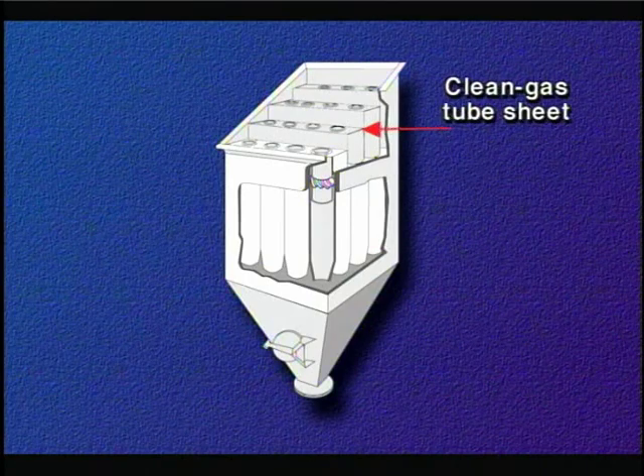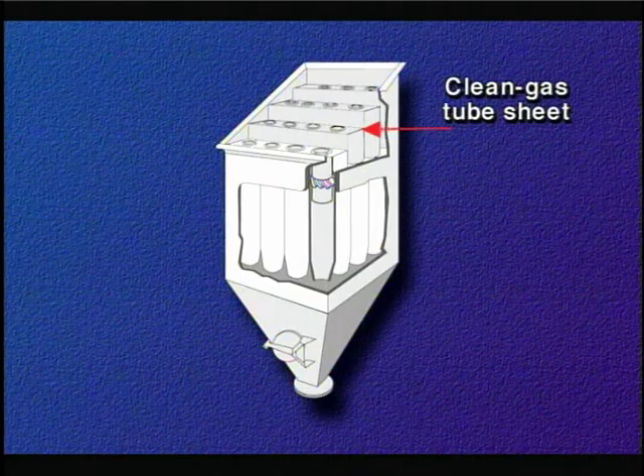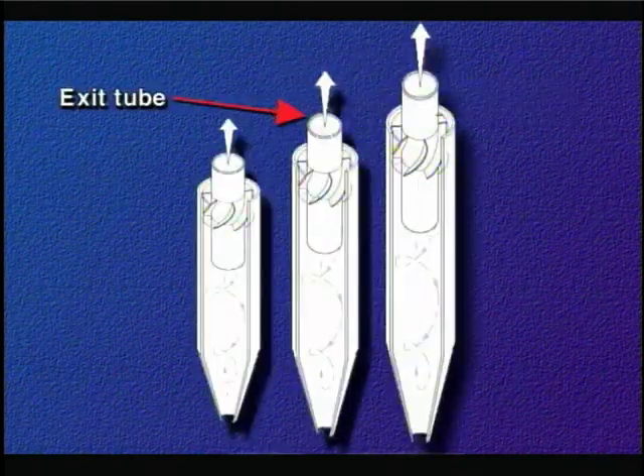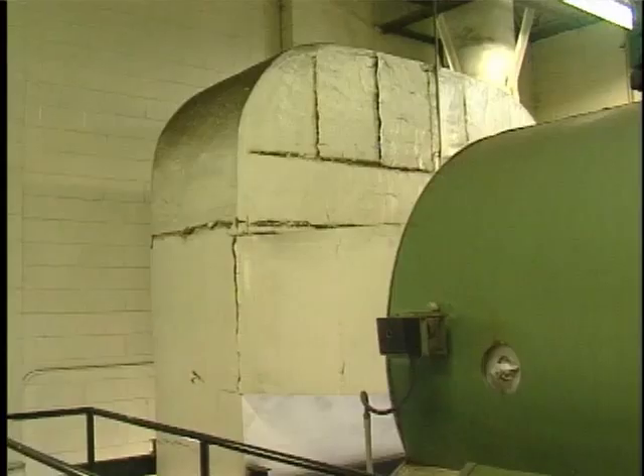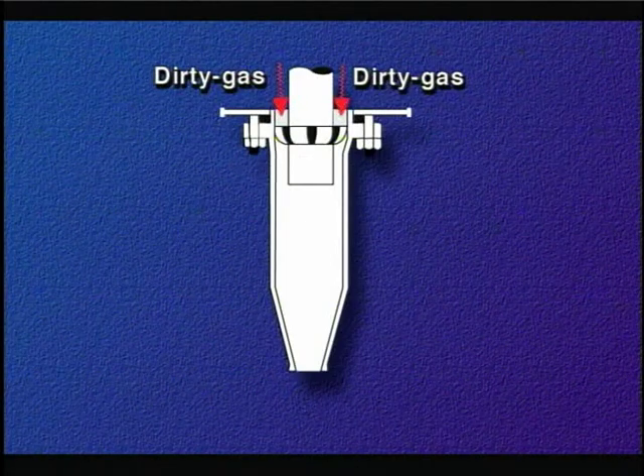The upper, or clean gas tube sheet, separates the inlet gas stream from the treated outlet gas stream. This tube sheet stair steps downward from the inlet or slopes at about a 45 degree angle in order to help evenly distribute the airflow into each row of cyclones. The exit tubes from each of the cyclones extend through the area of the entering gas stream and discharge through the upper tube sheet. The gas stream entering the multi-cyclone collector turns 90 degrees downward and enters the individual cyclones through the annular space between the body and the exit tube.